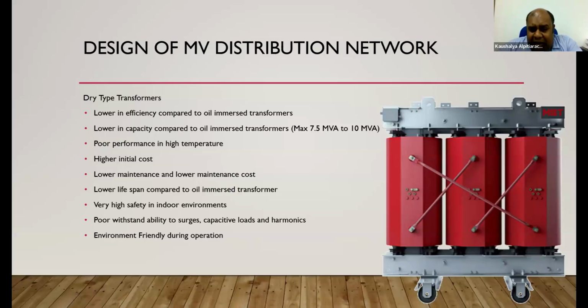Poor performance in high temperature. Applications where high temperature is produced at your transformer end. Higher initial cost, lower maintenance and lower maintenance cost, lower lifespan compared to oil immersed transformer, very high safety in indoor environments, poor withstandability to surges, capacitive loads, and harmonics. Environmental friendly during operation.